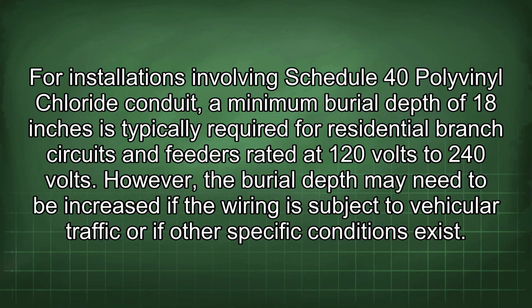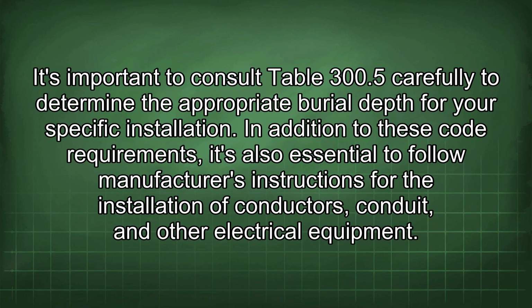For installations involving Schedule 40 polyvinyl chloride conduit, a minimum burial depth of 18 inches is typically required for residential branch circuits and feeders rated at 120 volts to 240 volts. However, the burial depth may need to be increased if the wiring is subject to vehicular traffic or if other specific conditions exist. It's important to consult Table 300.5 carefully to determine the appropriate burial depth for your specific installation.